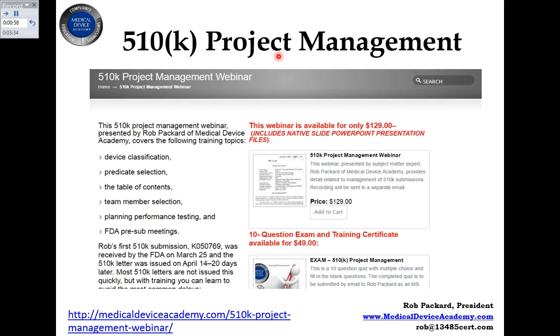This was just recorded a few weeks ago. The things that we talk about here are the things that everybody struggles with at the beginning of a 510K project. Identify the classification of the device. Make sure you identify appropriate predicates. You build your table of contents. You get all the sections lined up: here's what we're going to have in our submission. You put together a team of people that are going to write your 510K sections.